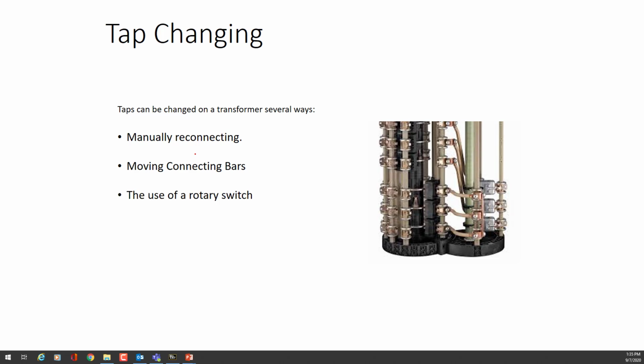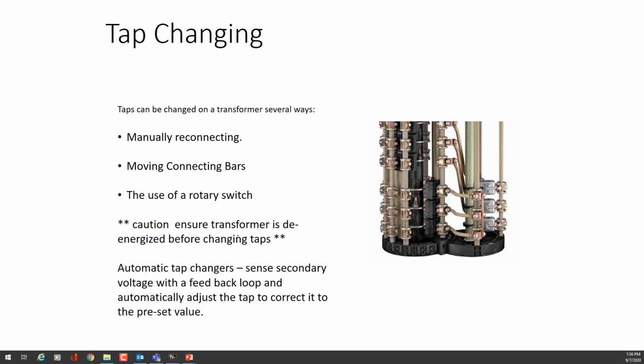Sometimes there's a bar you've got to move. The use of a rotary switch, that's another option out there, where it's terminated, and you can turn a rotary switch manually, and it'll change the taps for you. And caution, ensure the transformer is de-energized before changing taps. Automatic tap changers also exist. They sense the secondary voltage with a feedback or control loop, and automatically, it's motorized. They adjust the tap to any correct preset value. So that's about it on taps on a transformer.